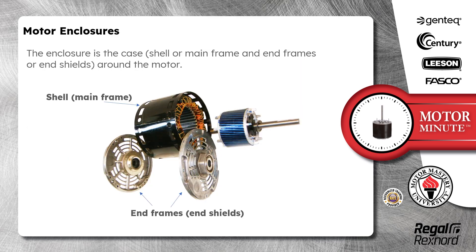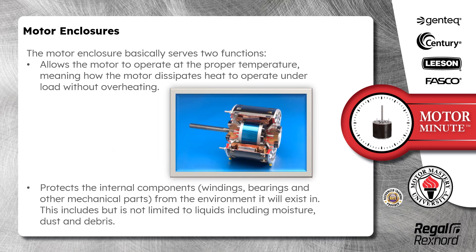The enclosure is the case, shell or mainframe, and end frames or end shields around the motor. The motor enclosure basically serves two functions: allows the motor to operate at the proper temperature, meaning how the motor dissipates heat to operate under load without overheating, and protects the internal components, windings, bearings, and other mechanical parts from the environment it will exist in.